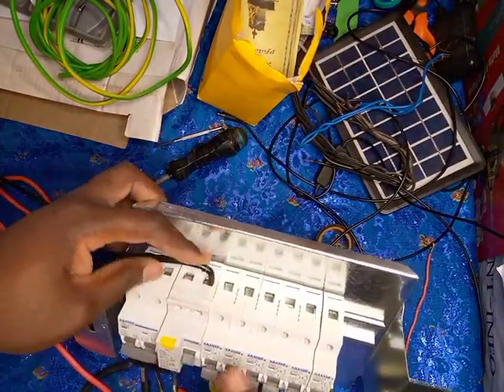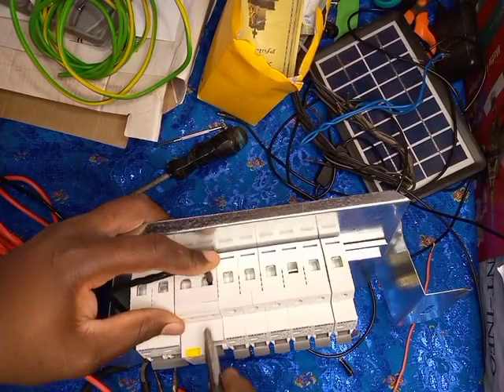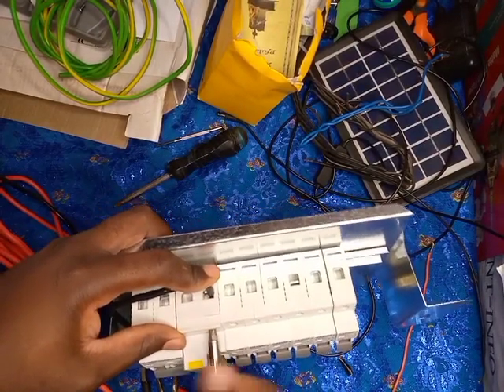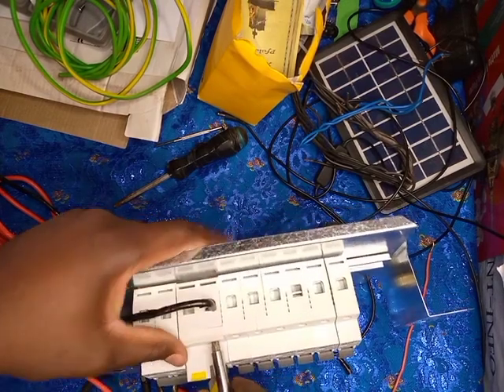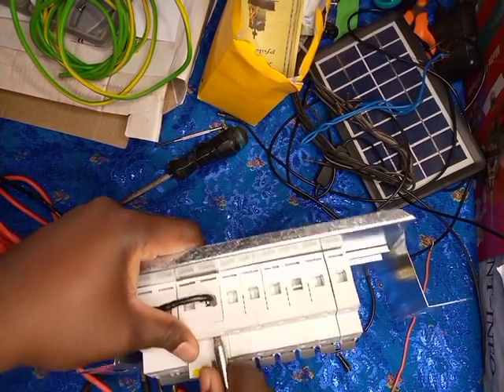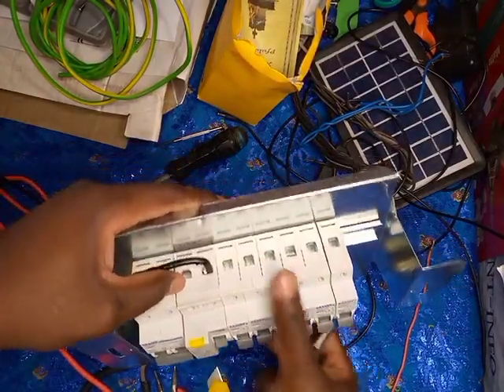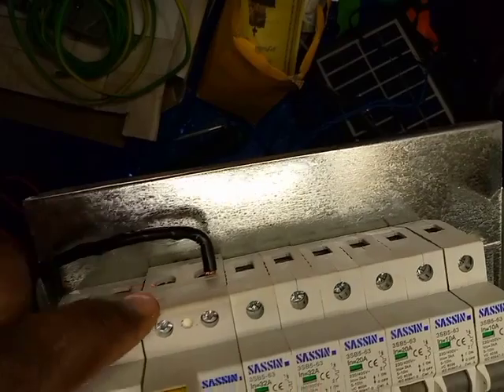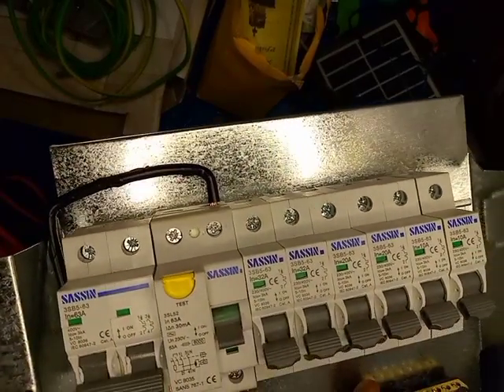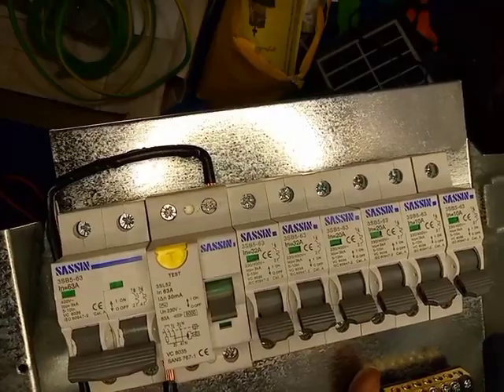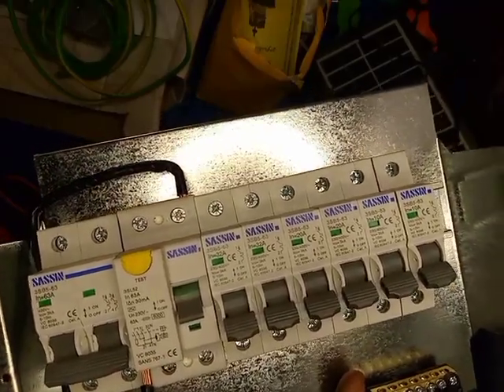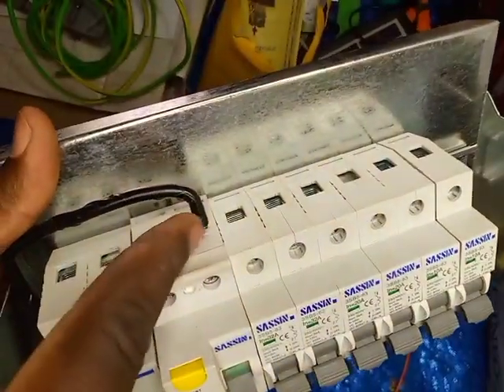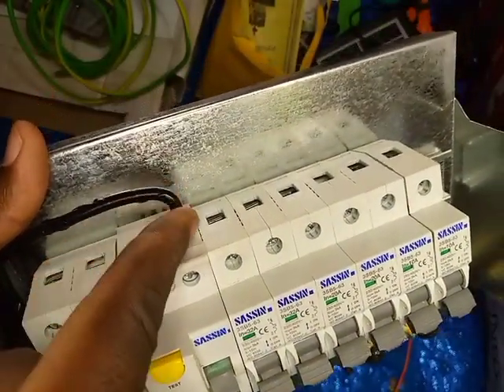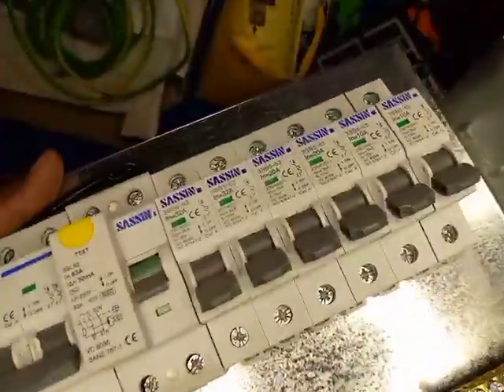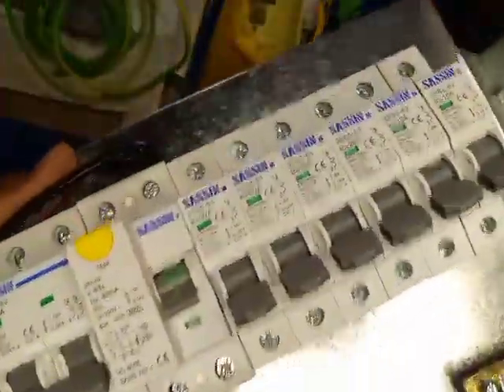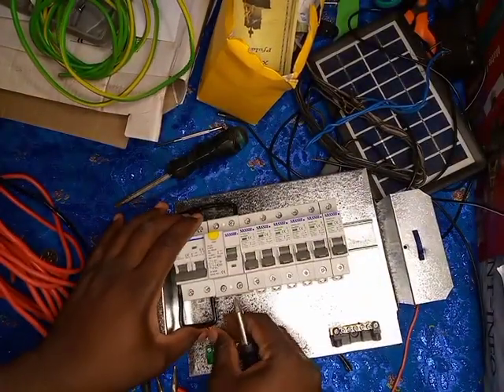Use the neutral, then you tighten it. Make sure that it's tight, but also make sure that the insulation does not get stuck in there, because this is something that causes short circuits in most cases, and can even make your circuit breakers burn. So when you cut your insulation, make sure you don't cut too much, but also not too little. Then this one will go to the neutral side, and again we'll have to tighten it.